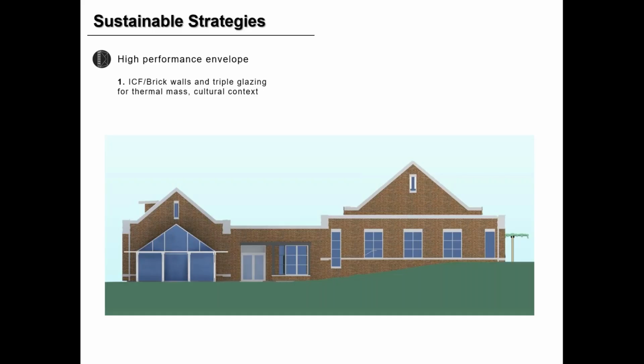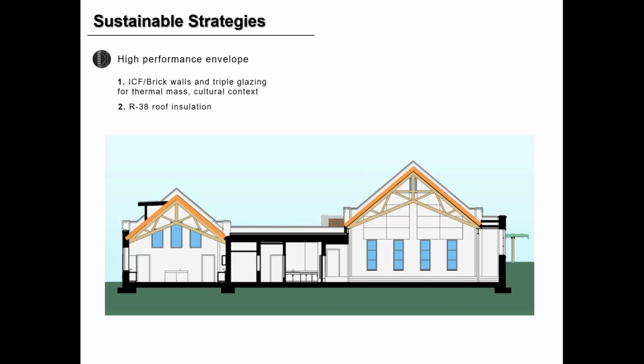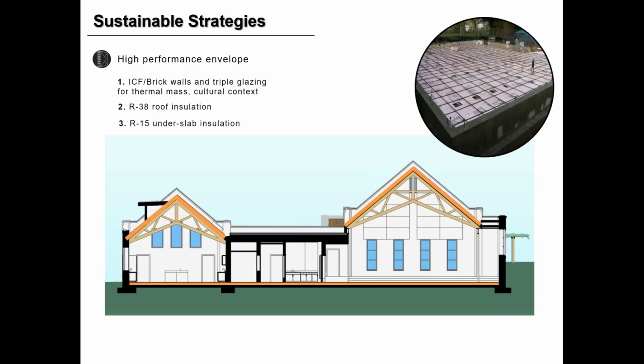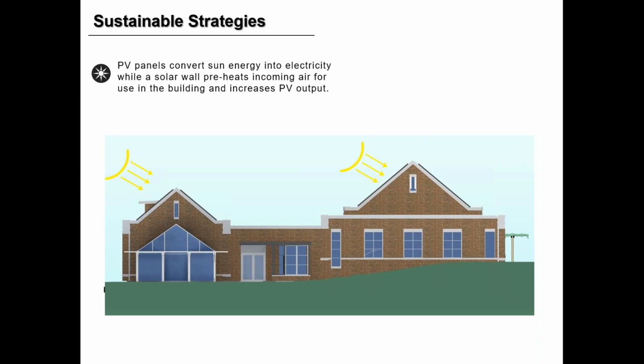Again, looking at following through with our procedures about reduction strategies first, we focus on the building envelope, one of those things we can control and make substantial improvements to for energy performance. You'll see this had triple glazing, thermal mass, and brick walls, improved roof insulation of R38, and underslab insulation of R15, which is important when you do in-slab radiant to separate yourself from the ground, so you're not putting that energy back into the ground, and the energy you put in goes up and into your space.